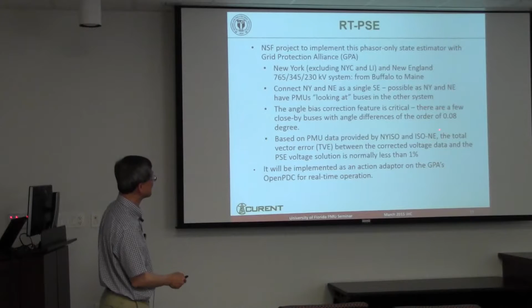Now we'll try to justify the angle bias correction, because there are portions of the network with so many generators in a small area that neighboring buses have a very small angle difference, on the order of 0.08 degree, while the native accuracy of the PMU is about 0.1 degree. So you can easily have this in the wrong direction, with flow appearing to go from a substation back into a generator instead of from generator out to substation. The total vector error is normally less than 1%.